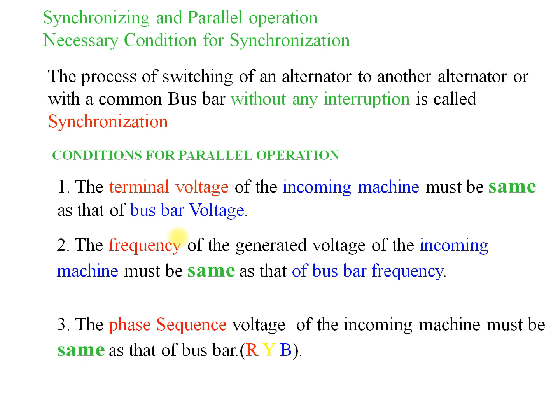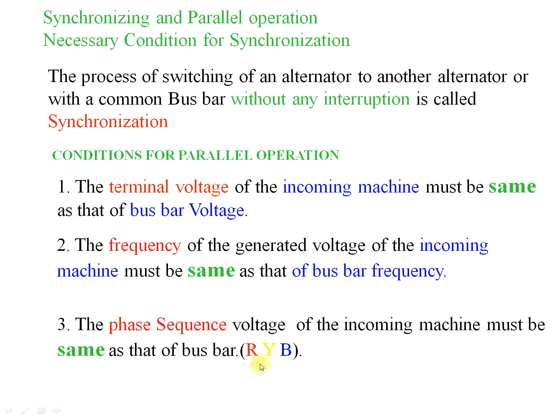The second condition is that the frequency of the generated voltage, or the frequency of the incoming machine, must be the same as that of the bus bar frequency. And the third one is that the phase sequence of the voltages should be the same as that of the bus bar. So the RYB sequence should be the same as that of the bus bar, and that should be met in the incoming machine.